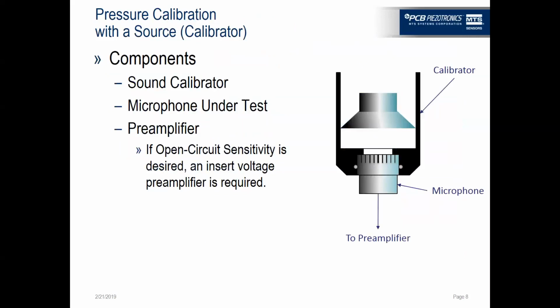So I'll talk about a method of calibration that we use here in the factory, and this is something that many of you should be using in the field when you're performing measurements, before and after your measurements, and that is a pressure calibration with a sound source or a calibrator. And the method and the components or the ingredients of this calibration are your sound calibrator, a microphone under test that you want to be calibrated, and in the case of all measurement microphones, it either has an integrated preamplifier, or if you have a setup where you have multiple cartridges that use the same preamplifier, you will use a separate preamplifier.